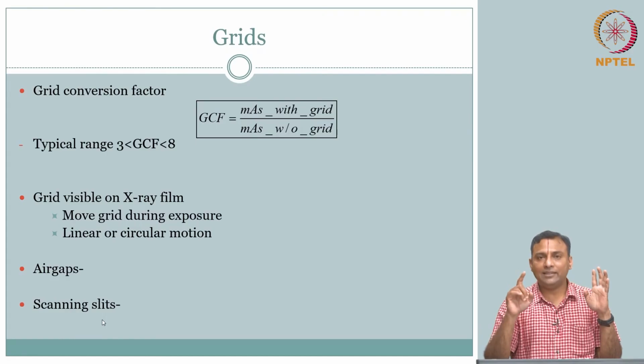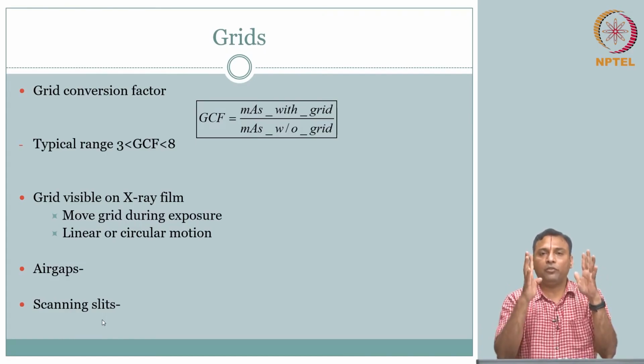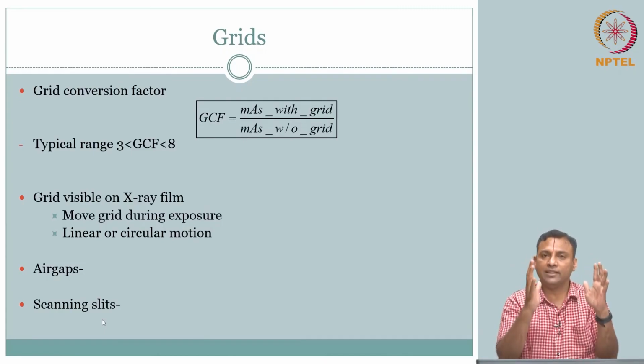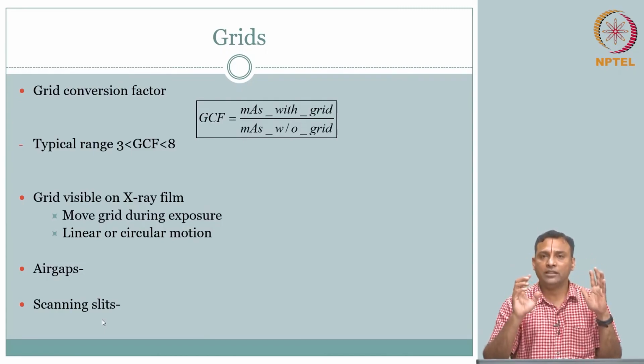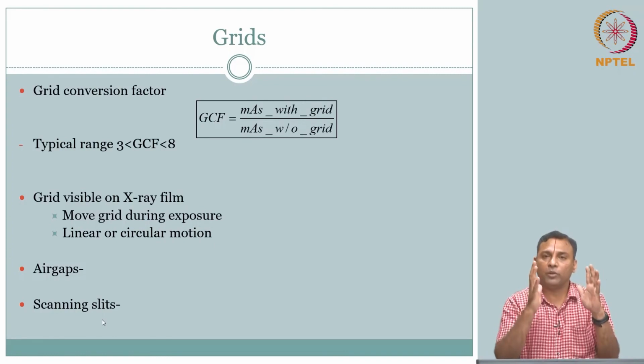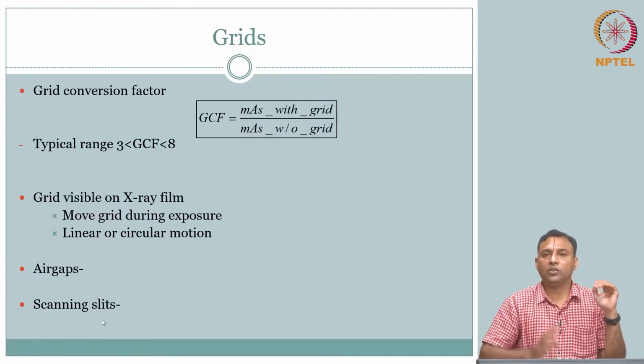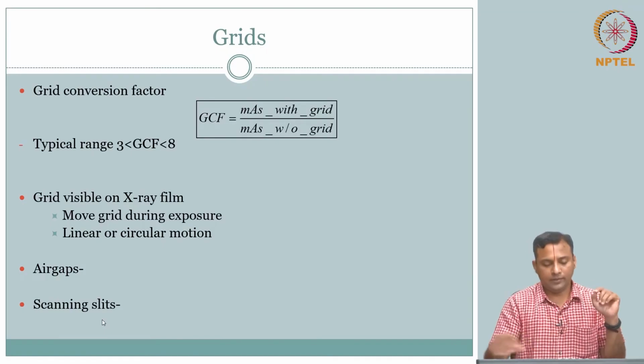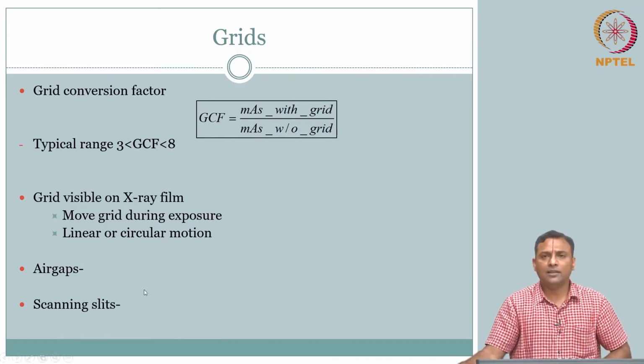But the only challenge is, the instrumentation is a little bulkier, you have to now synchronously move these two, and exposure is also increased because you are getting more shots at it while it is moving to different locations. Of course, time is also a little more because now you are scanning a few locations so that you don't have these shadow locations. That is the downside, but then you get a good signal to noise ratio. So this is again something that is used in higher end systems.